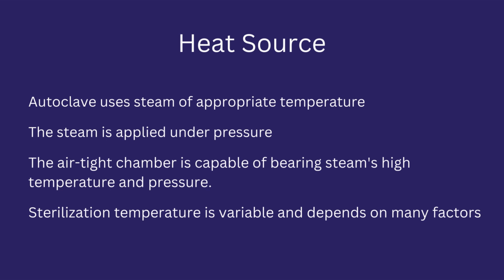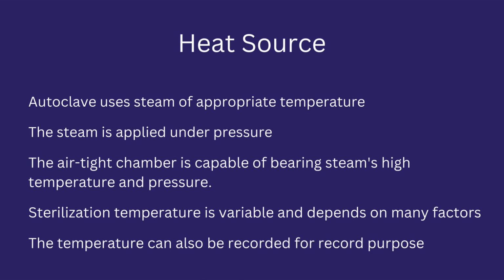The sterilization temperature of an autoclave is variable and mainly depends on the item being processed. If the item being processed can bear high temperature, it is subjected to high temperature. On the contrary, if the item being processed cannot bear high temperature, it is sterilized at low temperatures.